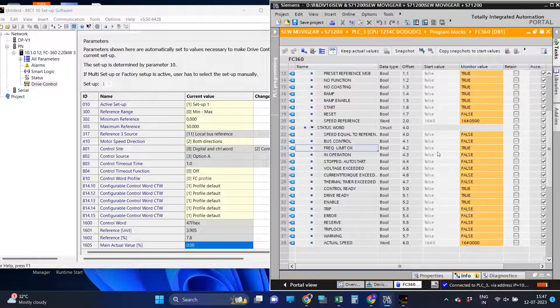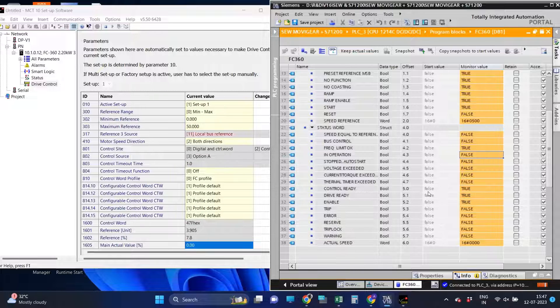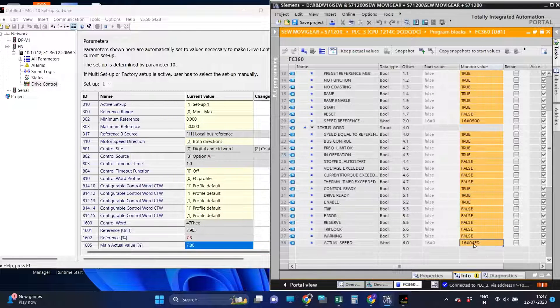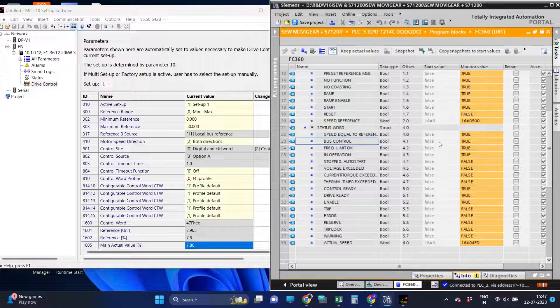Make sure the drive is in auto mode so that the status of a few bits turns to true and the motor will run. The following bits will be true: Speed Equal to Reference, Bus Control, and In Operation. These bits will turn their status to true only if the drive is in auto mode.